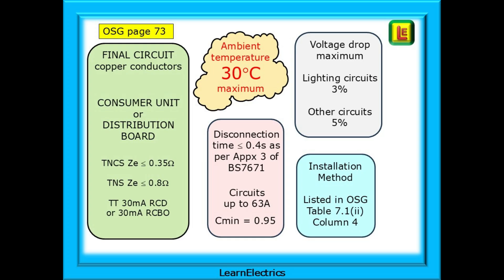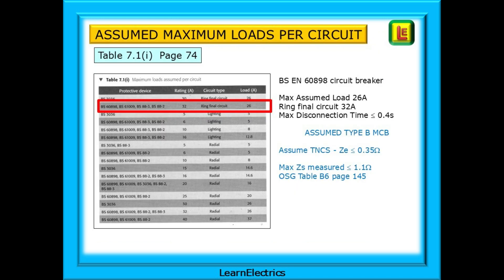At the end of the video I have included some useful visual memory joggers for the many different installation methods. Begin with Table 7.1.1 on page 74, finding the assumed maximum load for the circuit. What is the protective device and what amp rating is it? What type of circuit is it? For our example, we've chosen a 32-amp BSEN60898 circuit breaker to protect a ring final circuit. The table tells us that the assumed maximum load should be taken at 26 amps.